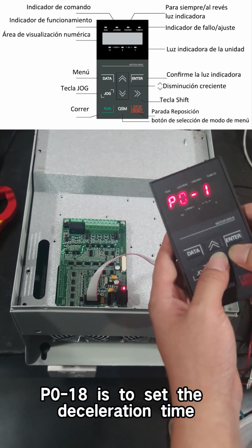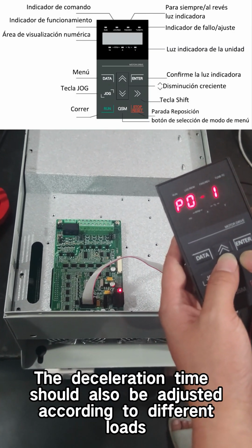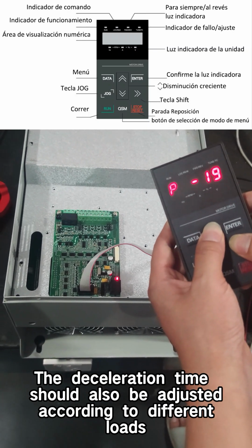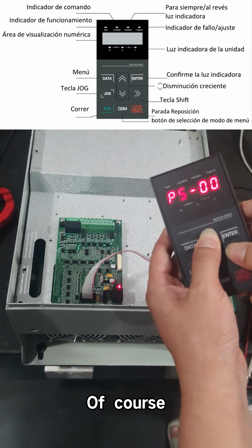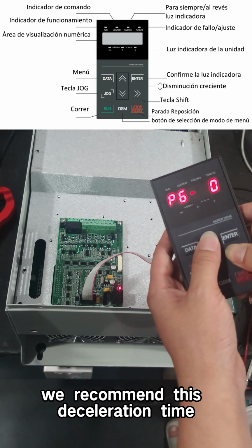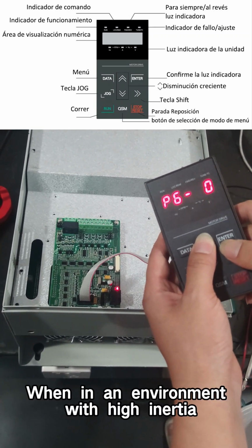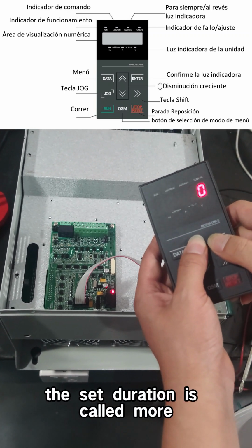P0-18 is to set the deceleration time. The deceleration time should also be adjusted according to different loads. Of course, we recommend this deceleration time: when in an environment with high inertia, the set duration should be longer.